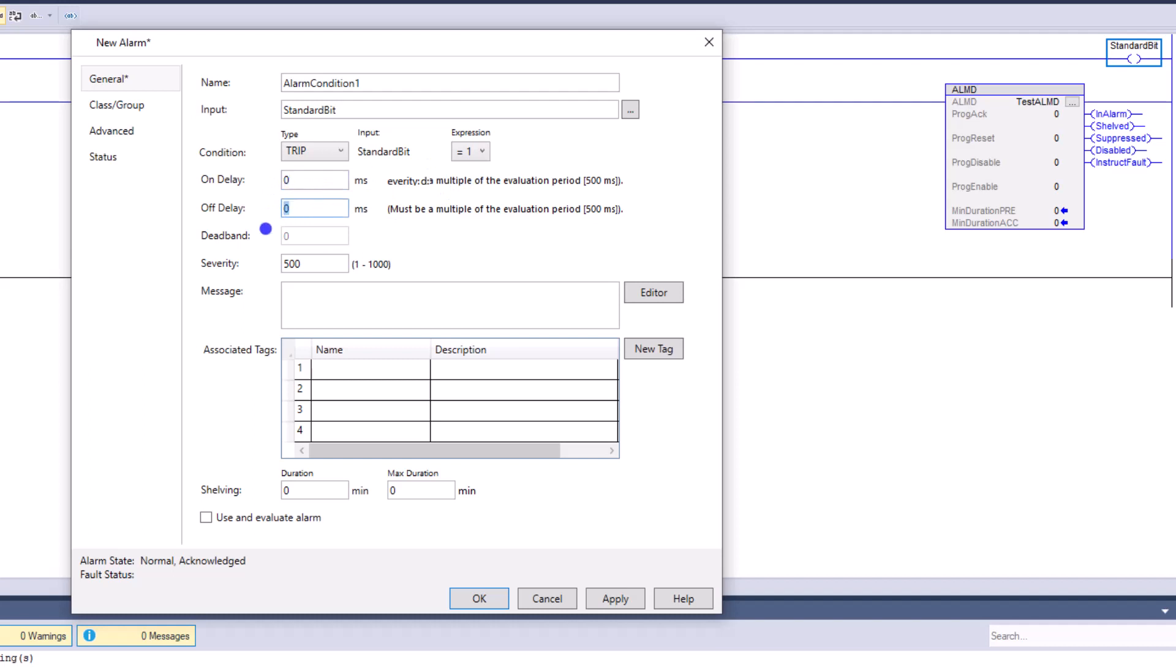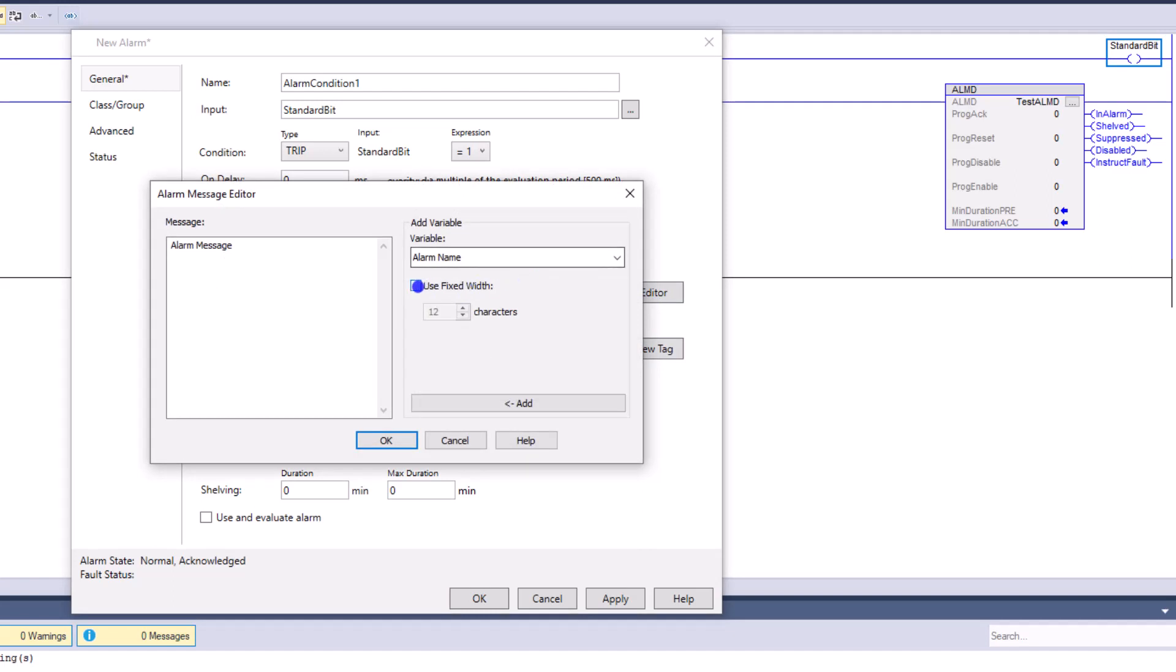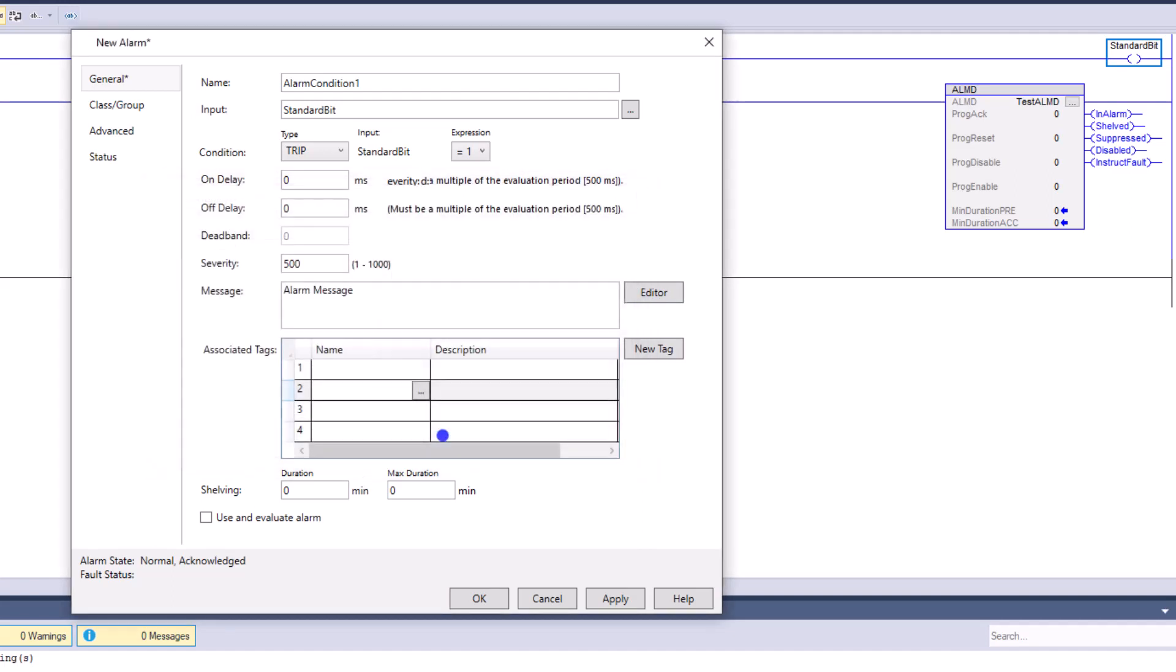You do have an on and off delay, but I will kind of go ahead and say, don't use that feature unless you really are in a heavy process or something like that, because it's already going to be delayed. Okay. You can change your severity just like you would in an ALMD. So, meaning if you want it from zero to, or from one to one, a thousand, a thousand being the highest severity. You can put your message in here. We'll just call this alarm message for our simple example. And you also could actually put in tags associated with that associated tags again, would be just like you would anything else in ALMD. You would add it just like that. In our case, we're going to use a simple message. We're not going to use any tags associated with that or nothing like that. You can use the use and evaluate alarm. We're going to leave that unchecked right now.